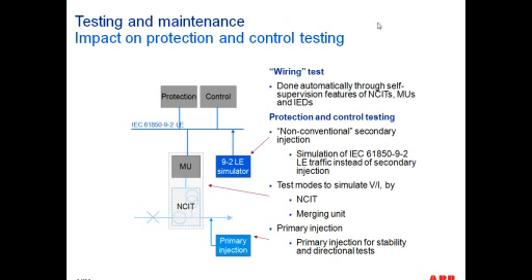So in the case of actually testing for these types of systems, available on the market today, there's actually from the 3 major relay tester manufacturers, they have 9-2 LE implementations available in such a way that you can test 9-2 relays today with the use of secondary injection via sample values in the form of Ethernet frames. So that is something that's very important, obviously, for the maintainability of the systems. And the good thing is that a lot of the interfaces are very, very similar to what a Doble 6150 or an Omicron CMC type device is. The only difference is that instead of having to wire voltage and currents to the relay, you essentially connect an Ethernet cable onto your network, and then you're able to do your testing that way.